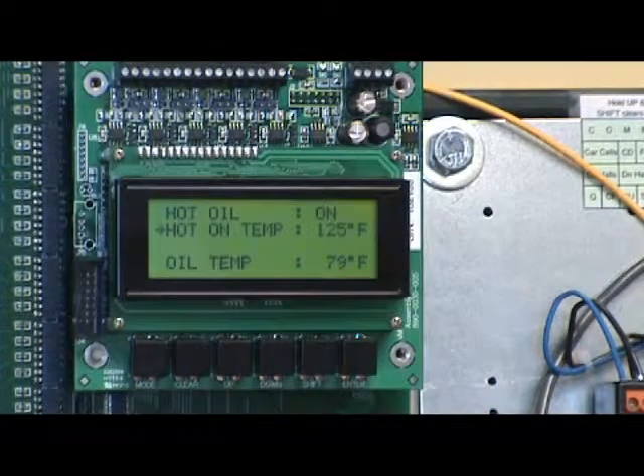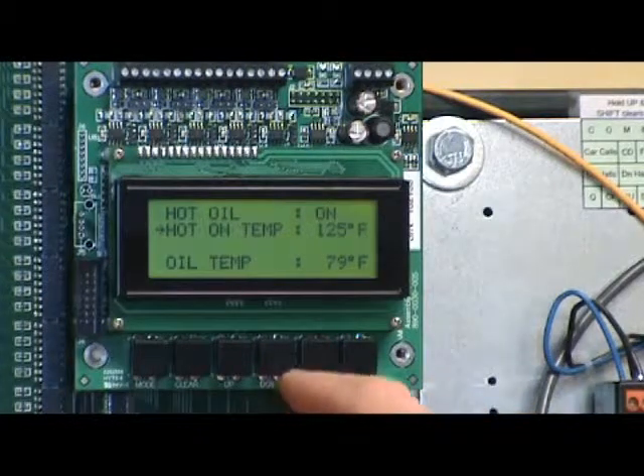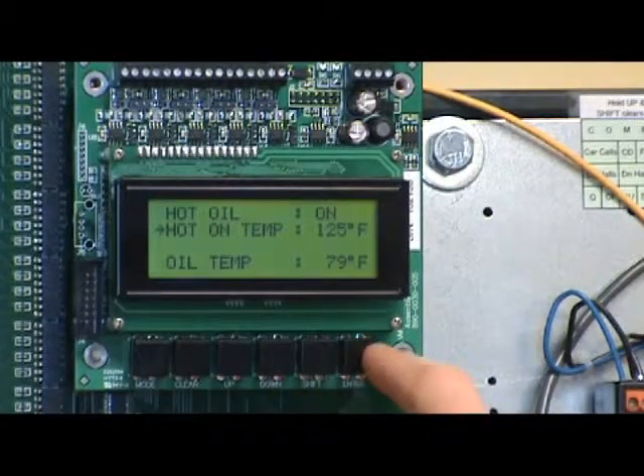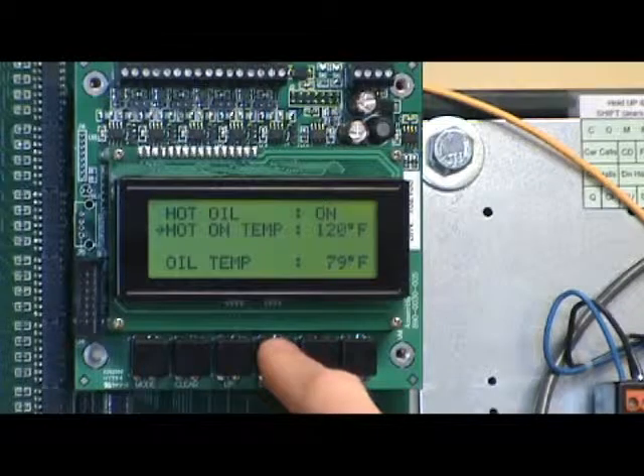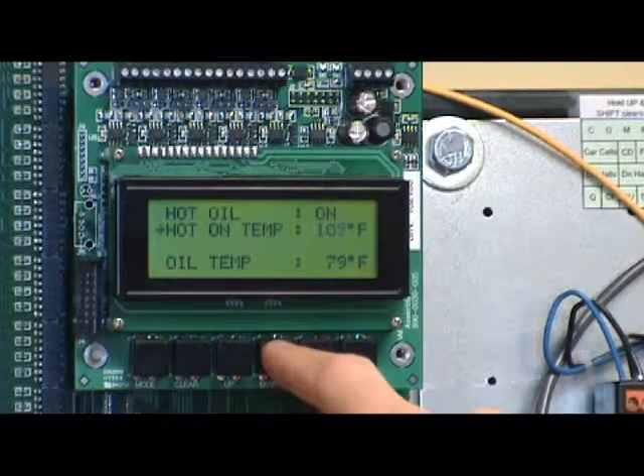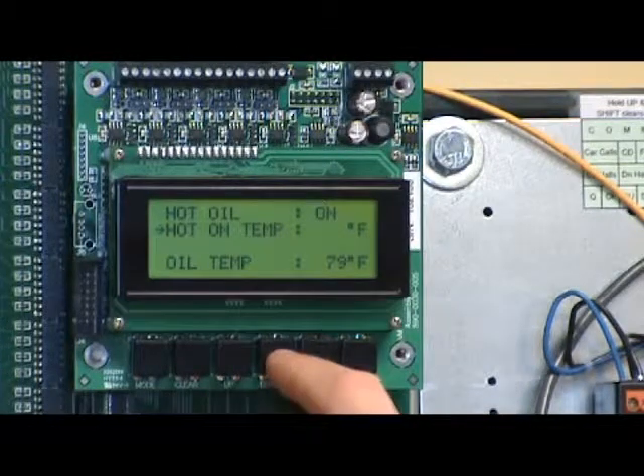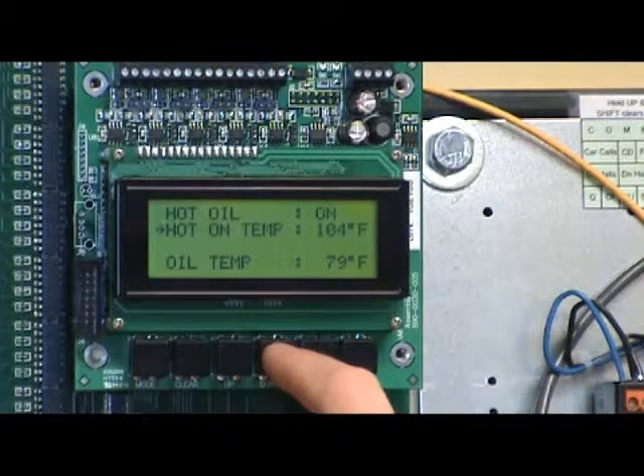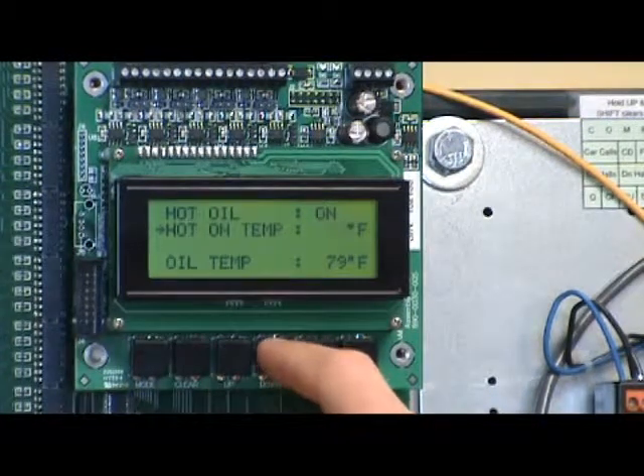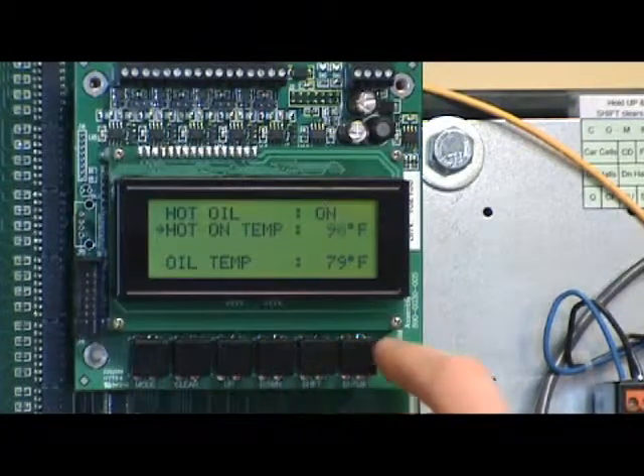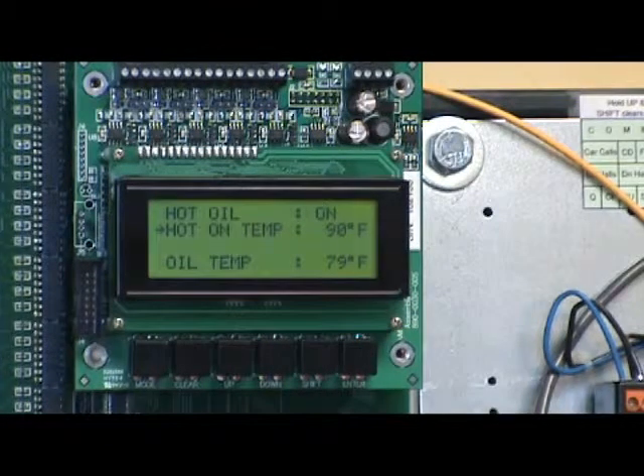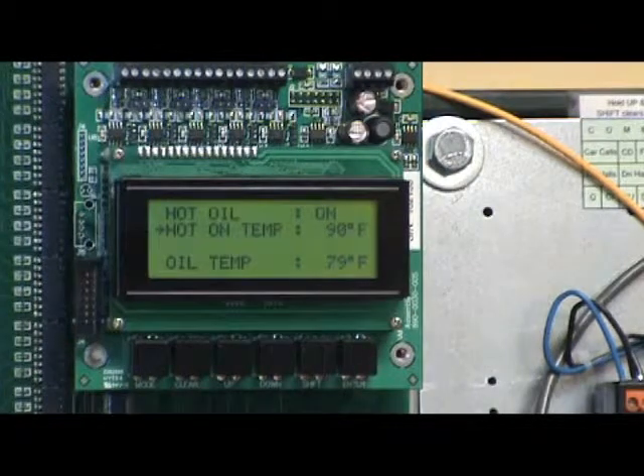One thing we can offer is that you can use this sensor as a temperature sensor for the ambient air temperature if you would like. And if you didn't put it in the oil, you can actually program this down to, I believe we have a lowest setting of 90 degrees. So if you have a customer that's not keeping the oil or the machine room temperature within the range that you need it, you can actually set this up and say, hey look, we're going to monitor the machine room temperature, and any time that this senses 90 degrees, we're going to shut down until the temperature in the machine room drops to 85 degrees.